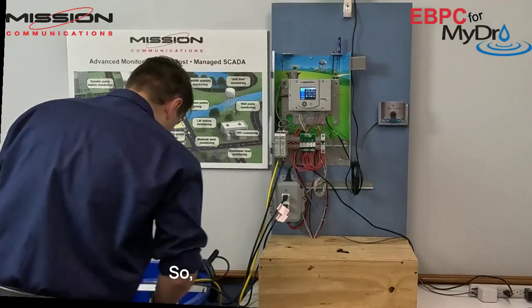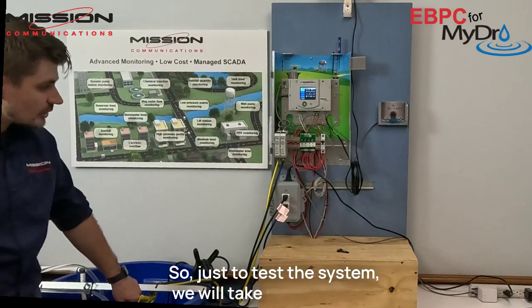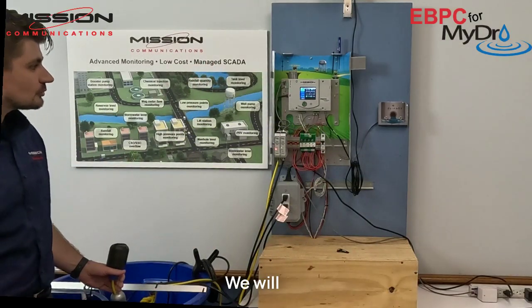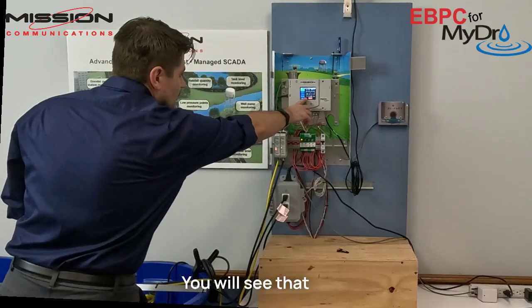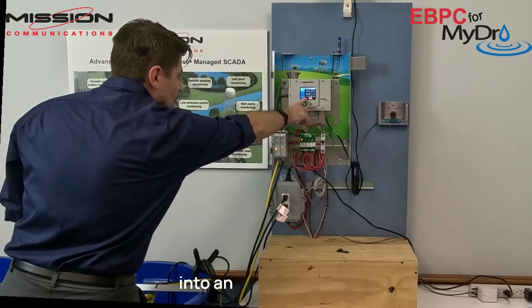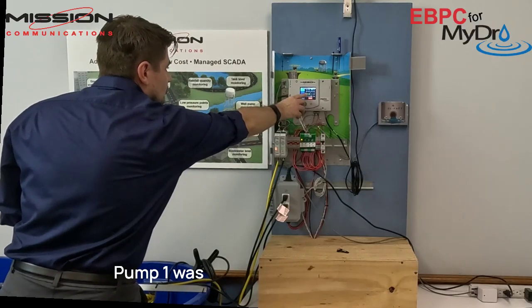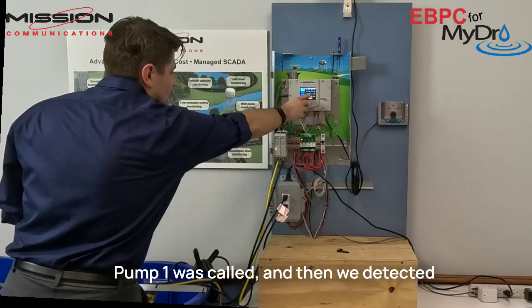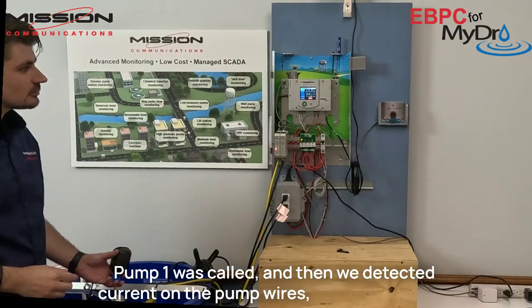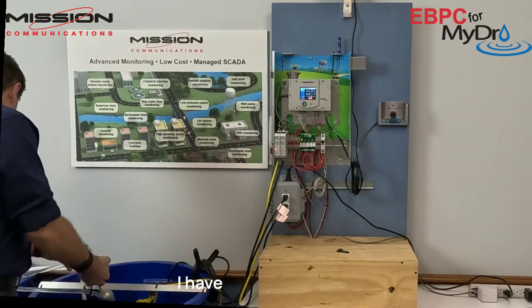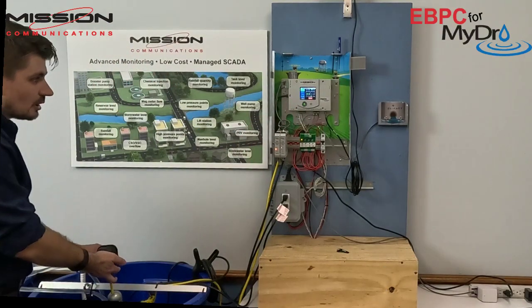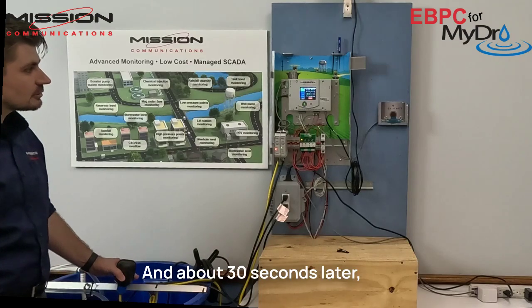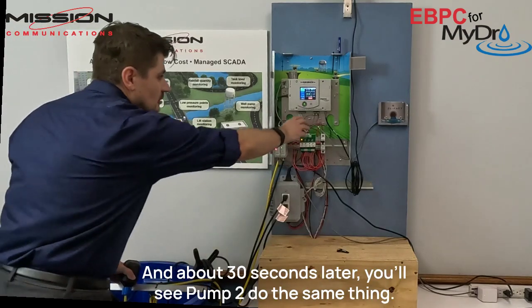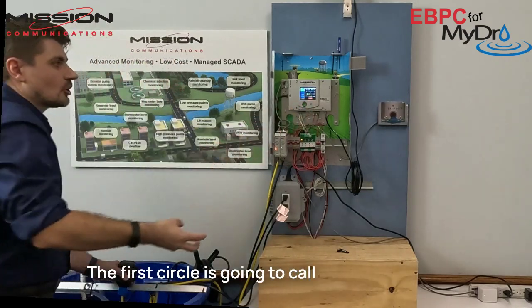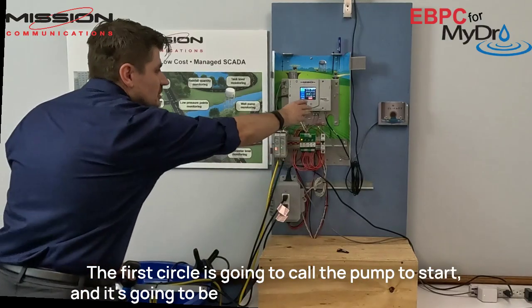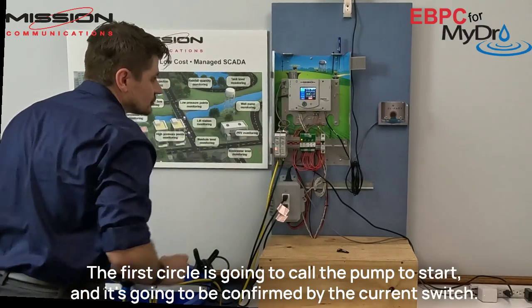So just to test the system, we will take our high float, we will tip it. You will see that it went into an off normal state. Pump 1 was called, and then we detected current on the pump wires, the pump starter. I have the pump running. And in about 30 seconds later, you'll see pump 2 do the same thing. The first circle is going to call the pump to start, and it's going to be confirmed by the current switch shortly after.